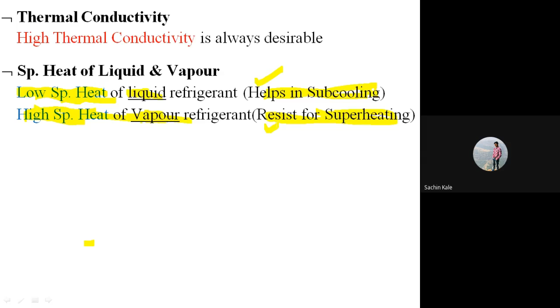So always keep in mind that while selecting the refrigerant, it should have low specific heat in case of liquid refrigerant and high specific heat in case of vapor refrigerant, because low specific heat in liquid refrigerant will help in subcooling, and high specific heat in vapor refrigerant will resist superheating.